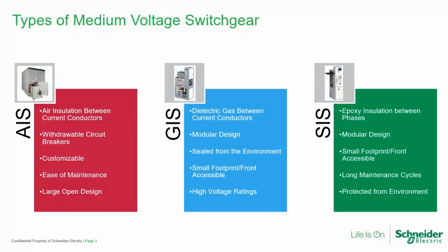When we're talking about medium voltage switchgear today, we're grouping it into three main large categories, categorized by dielectric insulators. The first style is air insulated switchgear, or AIS. Most of the traditional styles of medium voltage switchgear, both metal enclosed and metal clad, fall into this variety. Things like withdrawable vacuum circuit breakers in metal clad style switchgear fall into the grouping of air insulated switchgear.